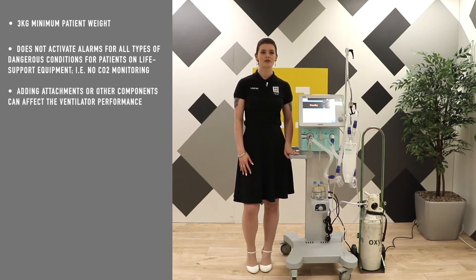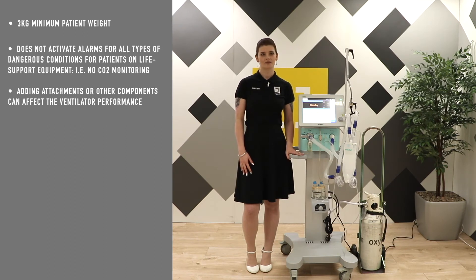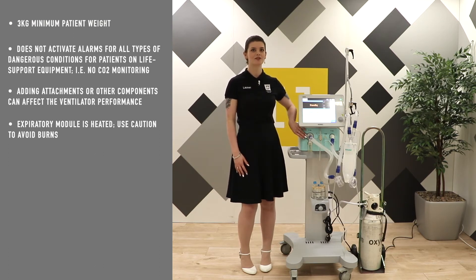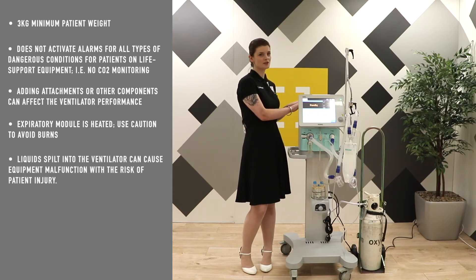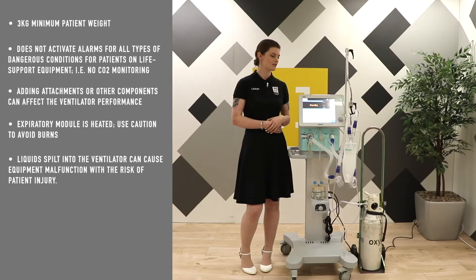Adding attachments or other components and sub-assemblies to the ventilator breathing system can change the pressure gradient across the breathing system, and such changes can affect the ventilator performance. The expiratory module here is heated, so use caution to avoid burning yourself when touching and removing it. Do not place containers of liquid such as the humidifier, water traps, or water reservoirs on top or above the ventilator. Liquids getting into the ventilator can cause the equipment to malfunction and risk patient injury.